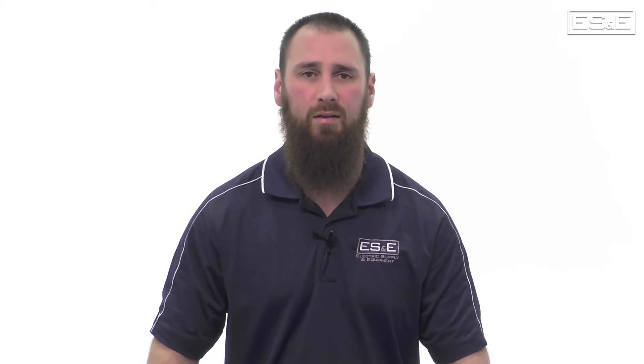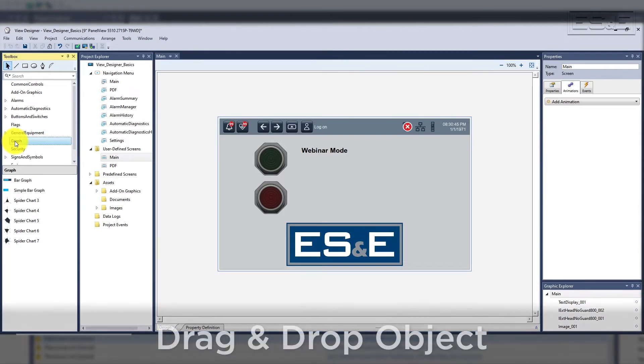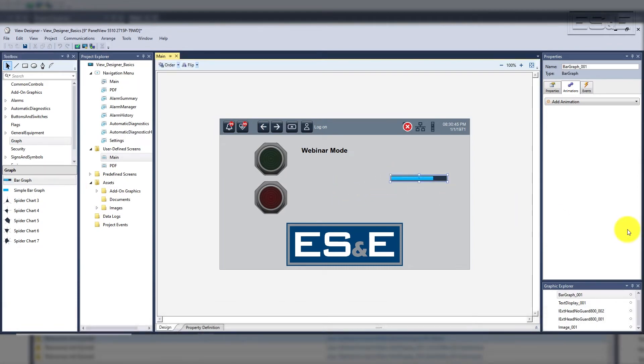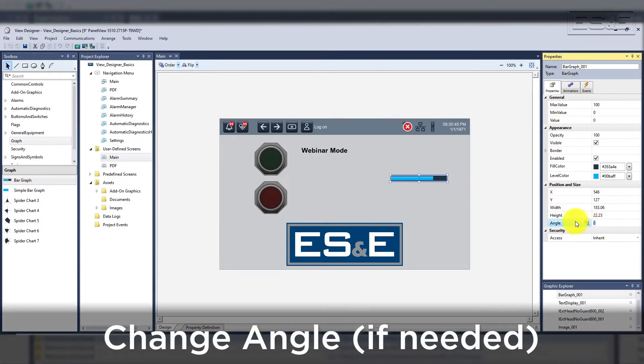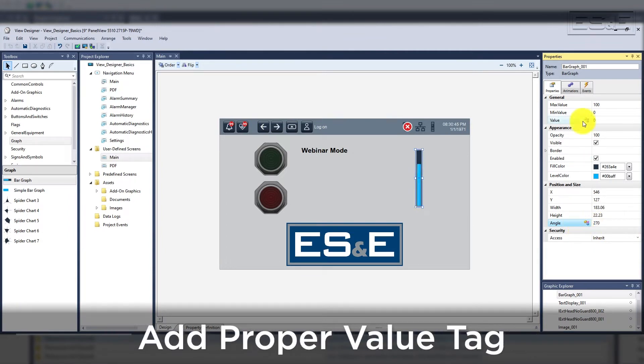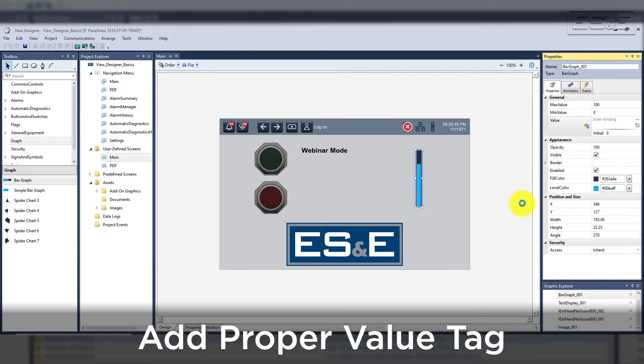The next object to add is a bar graph to simulate a tank level. This can be more easily done with a tank object under the general equipment folder, but we can always add an image of your exact equipment and then use a bar graph. Once we add the bar graph, it always has a horizontal orientation. In order to make it vertical, we need to edit the angle property — changing it to 270 degrees so that the animation fills upward, since the angle property works in the clockwise direction. If we put 90, it would result in the animation filling downward. The other property we need to bind is the value to our tag tank level.